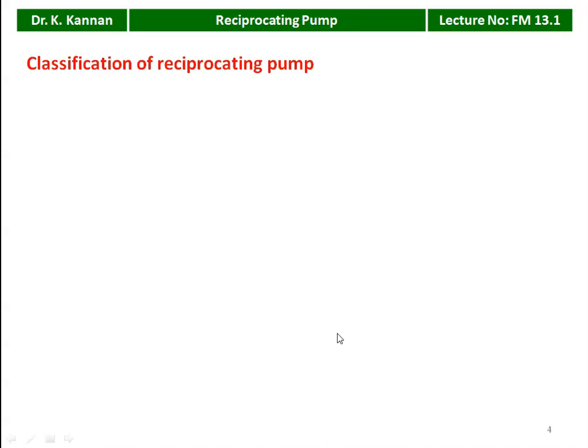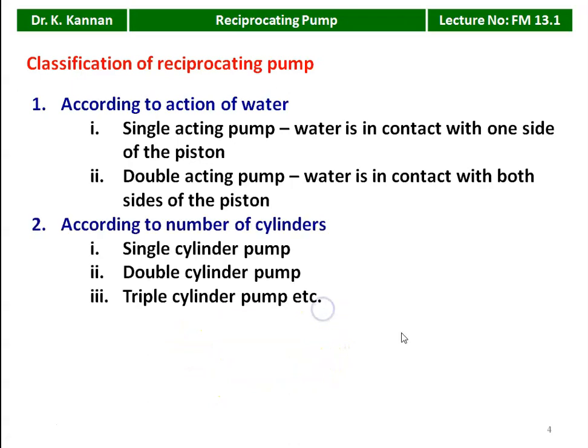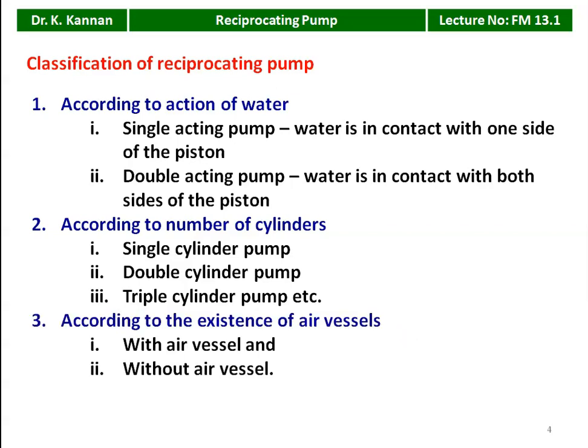The classification of the reciprocating pump: first, according to the action of water — it may be a single acting pump (water in contact with one side of the piston) or a double acting pump (water in contact with both sides of the piston). Based on the number of cylinders, it may be single, double, or triple cylinder pump, depending on delivery quantity and pressure rise required. According to the existence of air vessels, the pump may be with or without an air vessel — preferably with an air vessel so there will be continuous delivery of liquid.